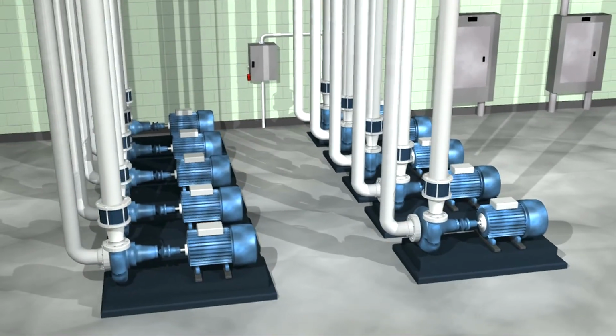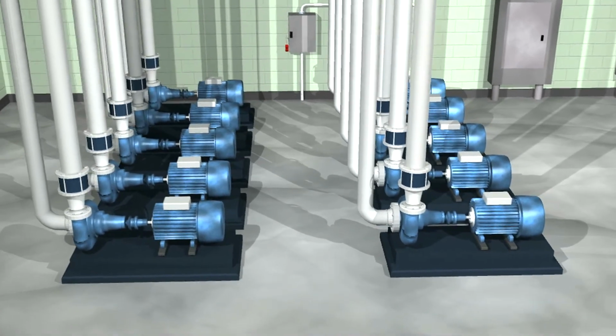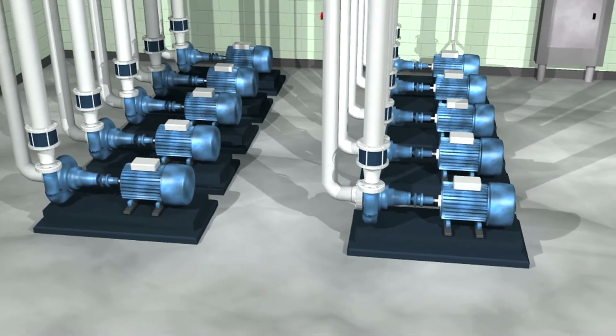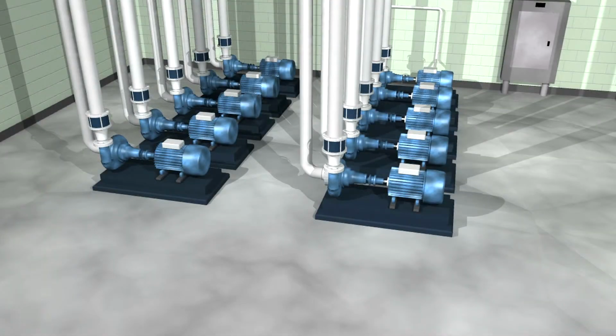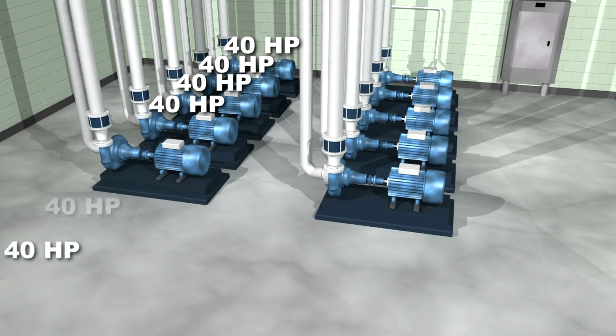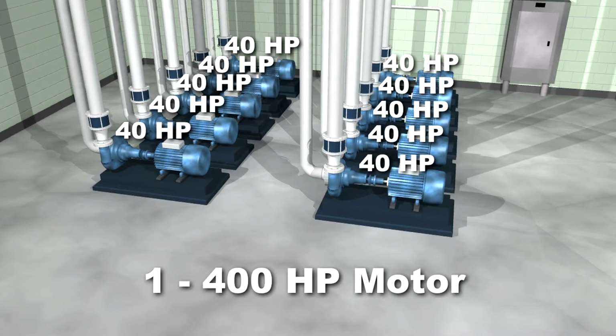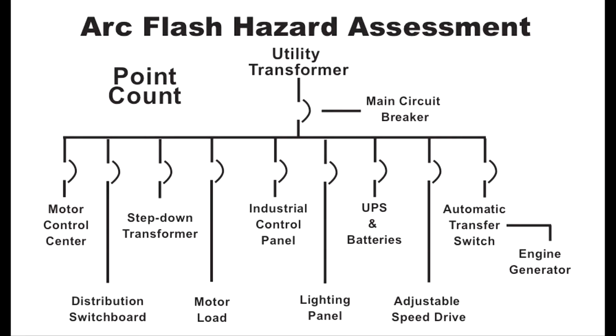If there are a large number of motors, less than 50 horsepower, they should be considered one motor. For example, if there are 10 motors within a motor control center, they should be added together and treated as one 400 horsepower motor.